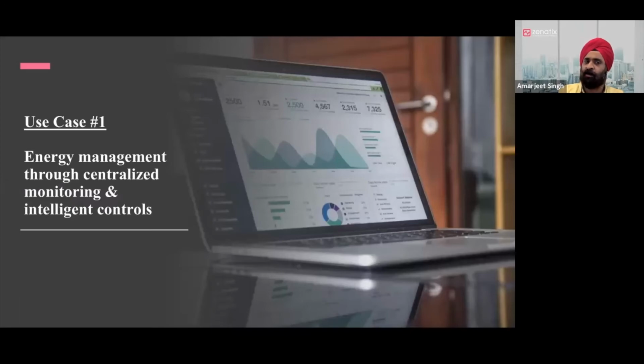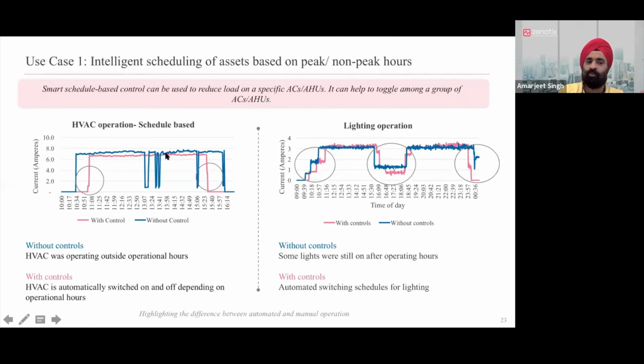The first insight is about more intelligent control. Here, the blue line shows control performed based on manual set points, where at a specific time of day equipment turns on, and at specific times it goes off. Versus more intelligent control, where you model the thermal profile of the building based on historical temperature and outside weather, and based on that decide the right time to switch equipment on or off, squeezing in more energy savings, whether it's HVAC or lighting operation.